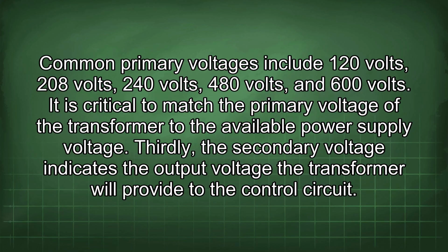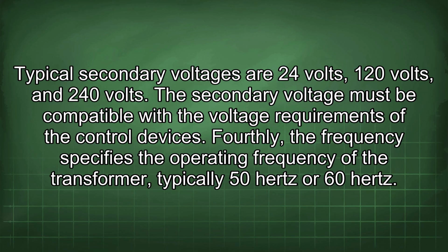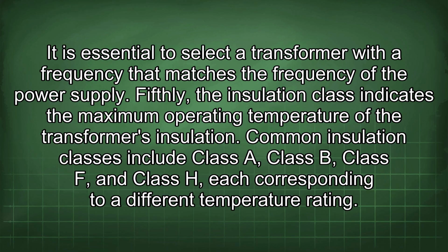Thirdly, the secondary voltage indicates the output voltage the transformer will provide to the control circuit. Typical secondary voltages are 24 volts, 120 volts, and 240 volts. The secondary voltage must be compatible with the voltage requirements of the control devices. Fourthly, the frequency specifies the operating frequency of the transformer, typically 50 Hz or 60 Hz. It is essential to select a transformer with a frequency that matches the frequency of the power supply.